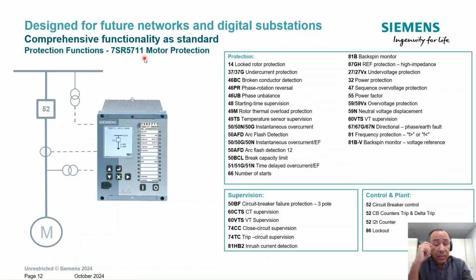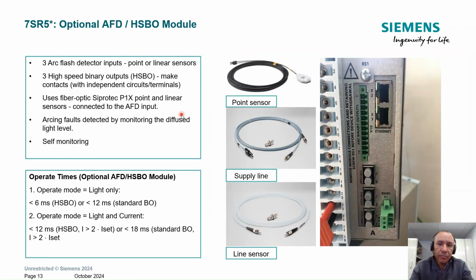The last option would be the 7SR5711. This device is a motor relay. We have this device with and without motor differential. This is more applicable for water utilities, where they have very big motors, like mining as well. And these are the 3 applications. First one, the feeder protection. Second one, the transformer protection. And the third one, the motor. Soon we're going to have line differential on this device as well.